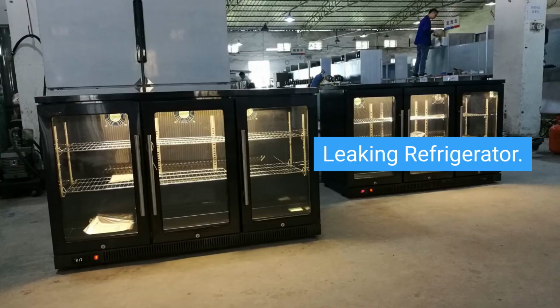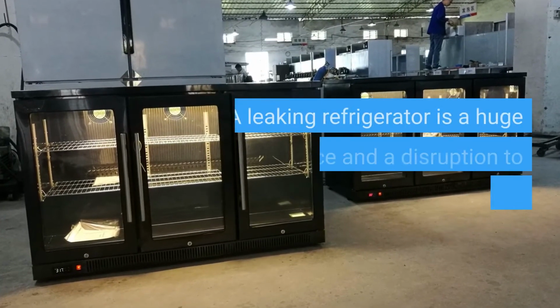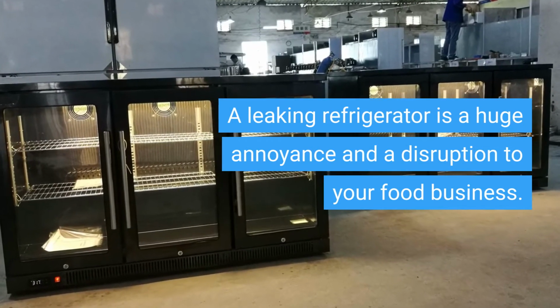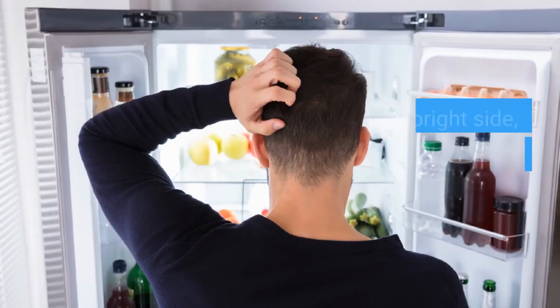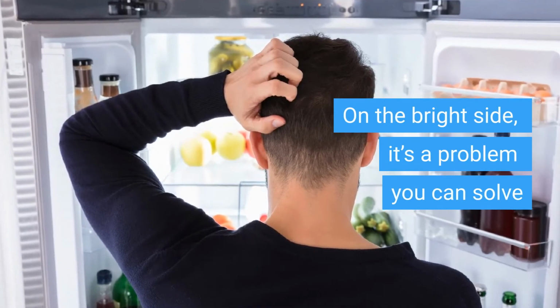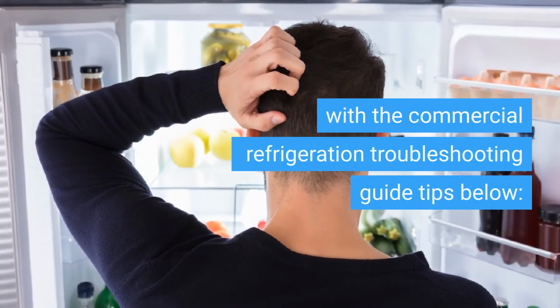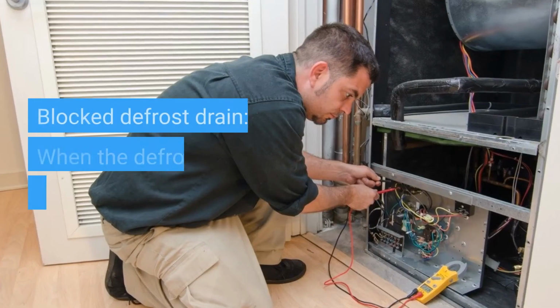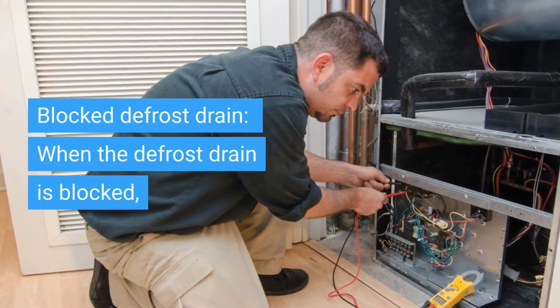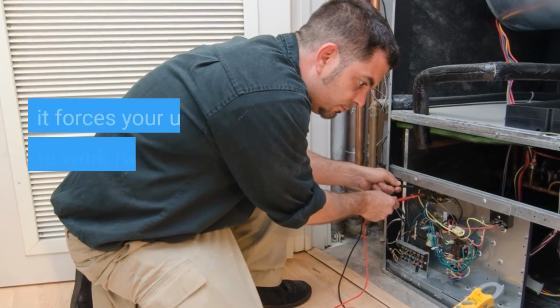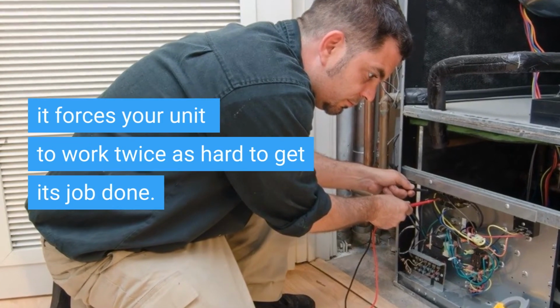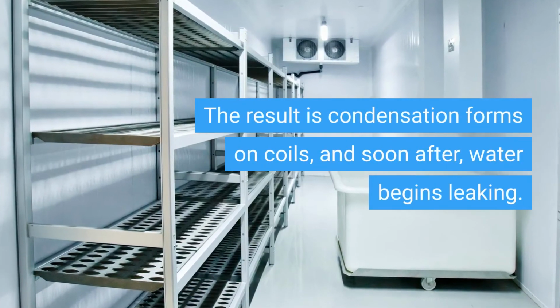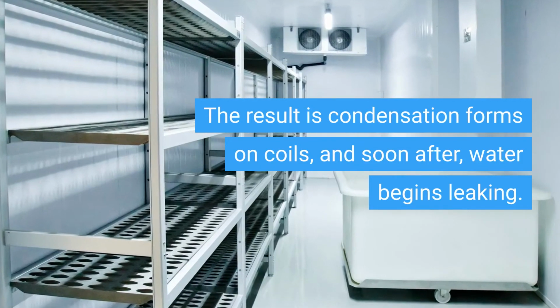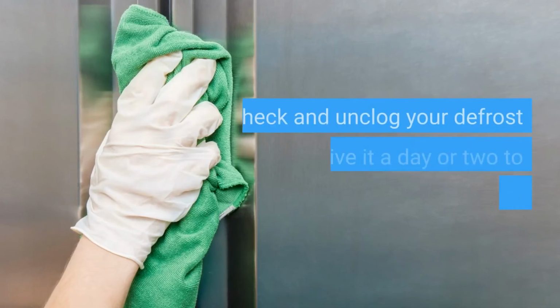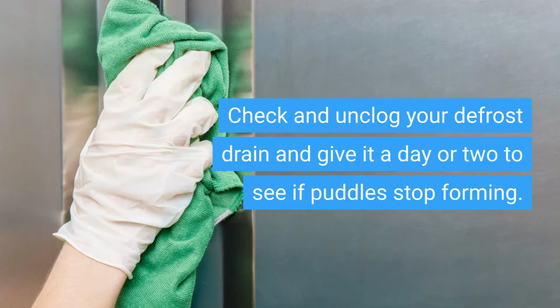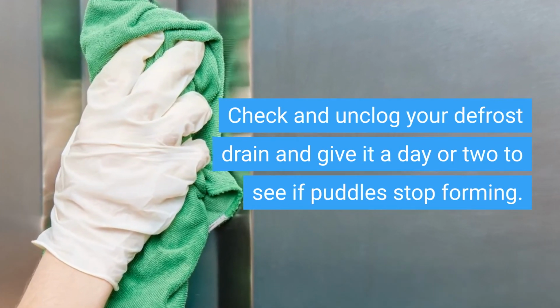Leaking refrigerator. A leaking refrigerator is a huge annoyance and a disruption to your food business. On the bright side, it's a problem you can solve with the commercial refrigeration troubleshooting guide tips below. Blocked defrost drain. When the defrost drain is blocked, it forces your unit to work twice as hard to get its job done. The result is condensation forms on coils, and soon after, water begins leaking. Check and unclog your defrost drain and give it a day or two to see if puddles stop forming.